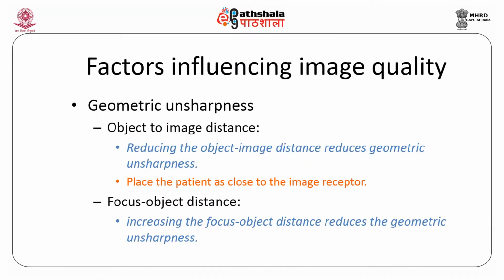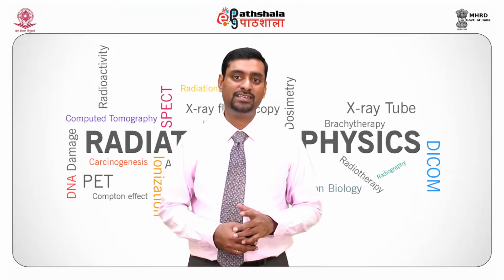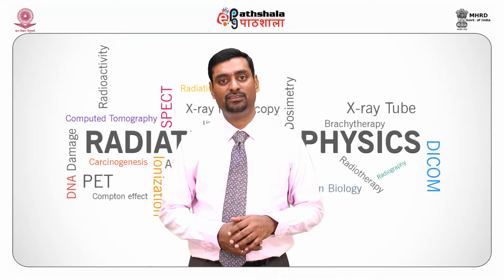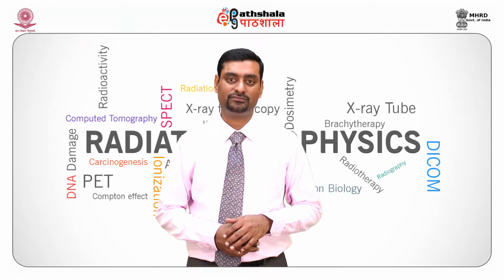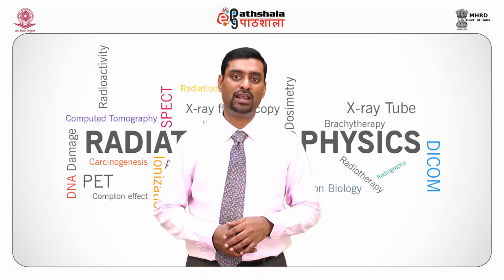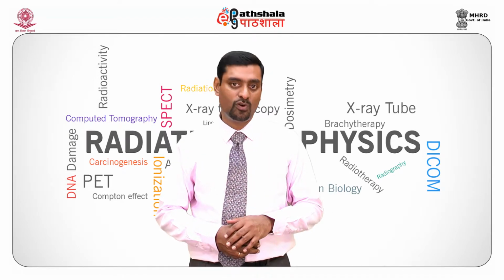The second part of geometric unsharpness is the object to image distance. Reducing the object to image distance reduces geometric unsharpness. Place the patient as close to the image detector as possible. Generally during a C-arm procedure done in an operation theatre, it's always good to keep the detector close to the patient. Or during an interventional procedure, the image intensifier or flat panel detector should be as close as possible to the patient so that we have good image quality.